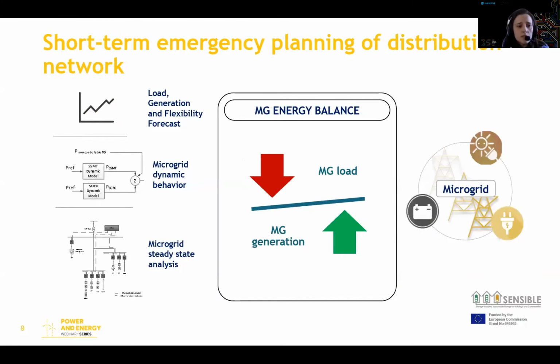So we developed this tool that tries to ensure the effectiveness of the control strategies and ensure that we have enough storage capacity to provide frequency and voltage regulation. In order to do that, we will try to define the best control strategies of the grid supporting devices, such as other flexible loads or even smaller storage devices that are connected to the system that can support some part of the loads or even charge during some time if we have a lot of renewable energy sources, to try to avoid the discharge of the grid forming storage devices.